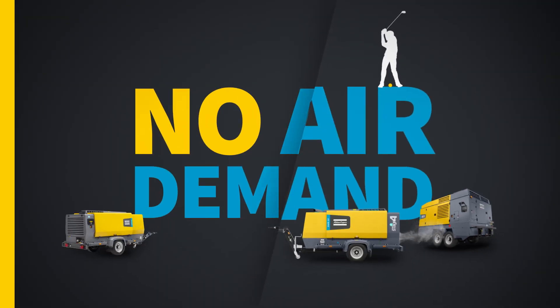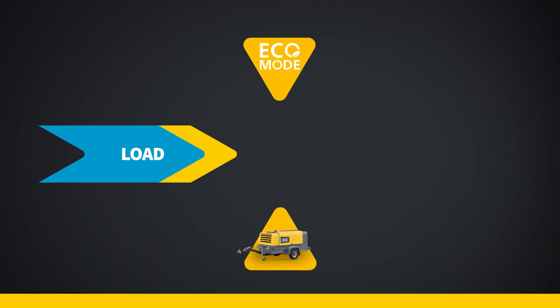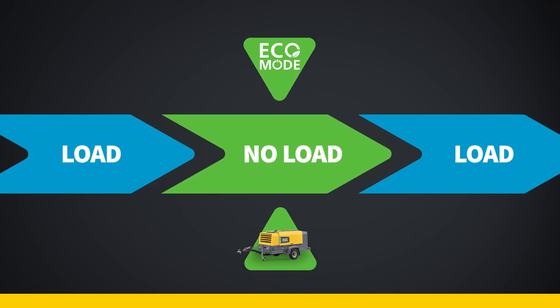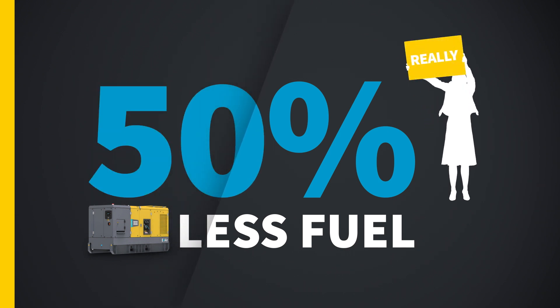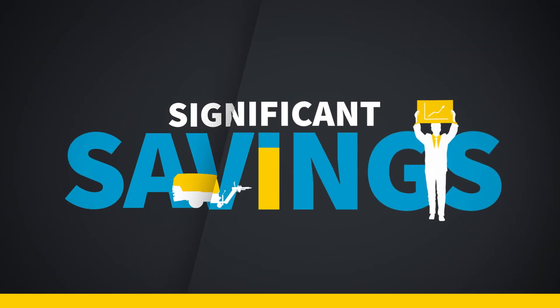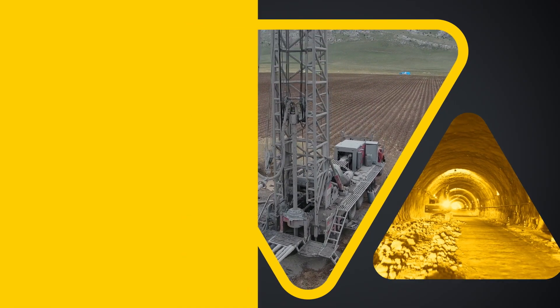What exactly are the benefits? If your application has a longer period without air demand, your compressor will go into unload mode — but it will still burn fuel. Thanks to the Eco Mode function, however, the compressor will automatically switch from unload to no load. During this no-load time, the compressor consumes up to 50% less fuel. Since 80% of your compressor's operating costs come from fuel, this leads to significant savings.